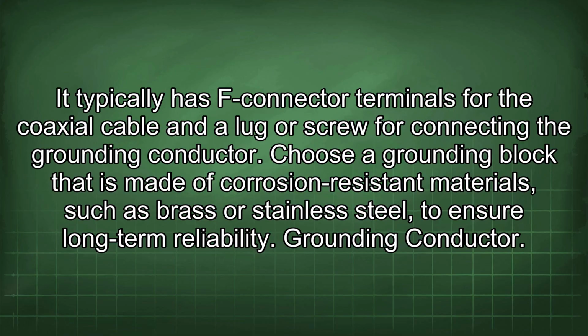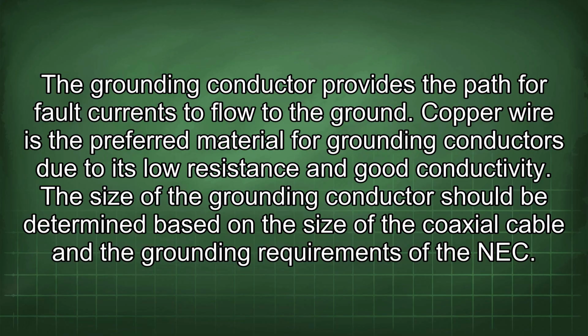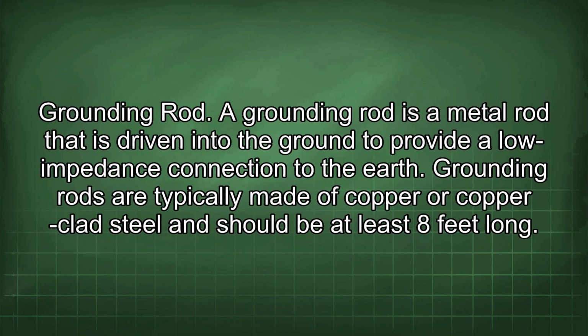Grounding conductor. The grounding conductor provides the path for fault currents to flow to the ground. Copper wire is the preferred material for grounding conductors due to its low resistance and good conductivity. The size of the grounding conductor should be determined based on the size of the coaxial cable and the grounding requirements of the NEC. Grounding rod.